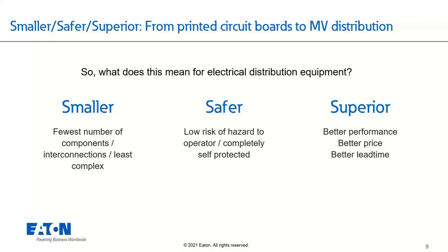It also is going to mean the least number of interconnections. So when we're talking about ways to do protection systems, obvious selections often are vacuum interrupters or vacuum breakers, where you have this electronically trippable component. You might have some sensors and some relaying combined in that. But if I'm going to have to tie all that in separately on site, it doesn't exactly make it not complex.